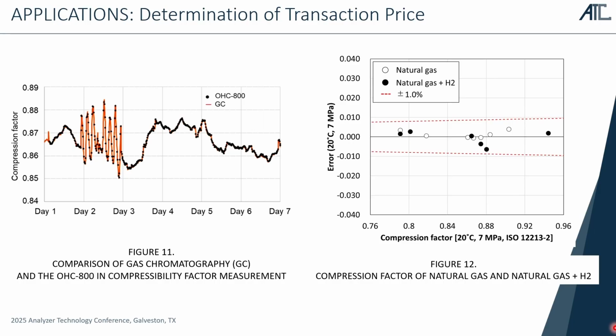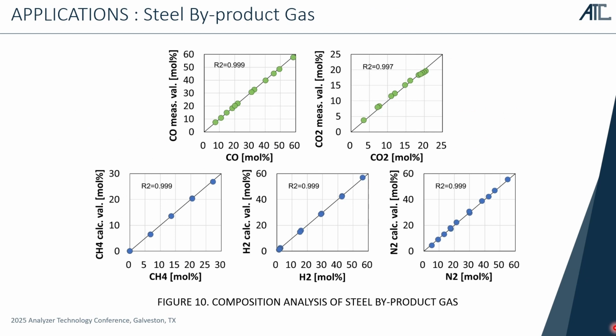And this is the last one, a steel byproduct gas measurement. In the steel industry, there are coke oven gas, blast furnace gas, and converter gases. There is some recovered energy in the steel industry. And we have a technology to measure the BTU value and the gas components of these 5 gases listed here. And the accuracy is within 2%. Traditionally, the GC is used for this application, but we can substitute it with our technology.